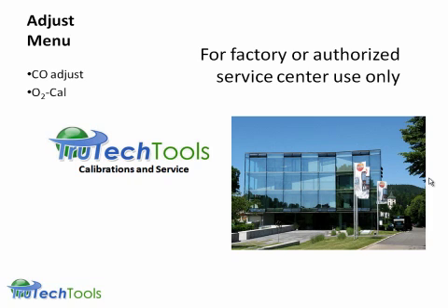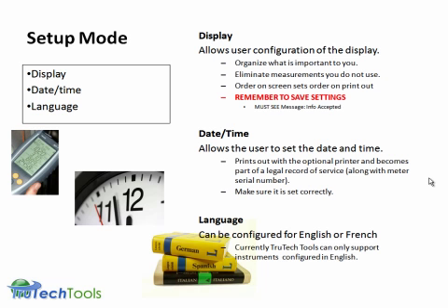We talk about the adjustment menu. That's really for factory calibration. That's your CO adjust and your O2 adjust. TruTech Tools is a factory authorized service center. You can also send it out to Testo for calibration and service, but we typically have very quick turnaround times.